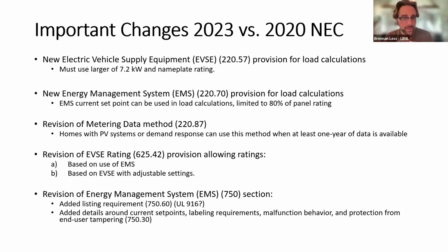We have a new provision that addresses energy management systems in load calculations. That's section 220.70. This basically boils down to saying that you can use the current set point of the EMS in your load calculations, and that's more or less limited to 80% of the panel rating or the protective rating for whatever circuits are being controlled.